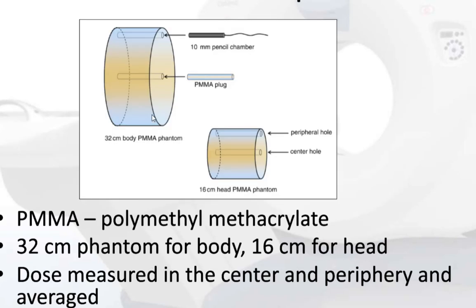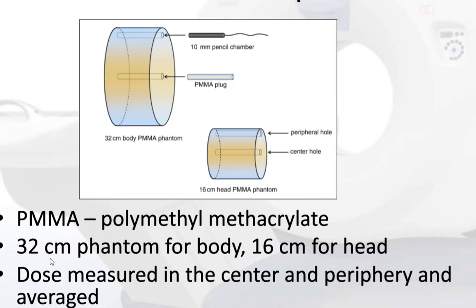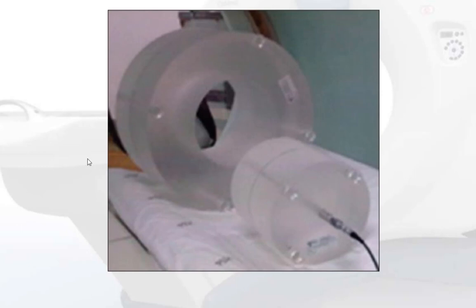The phantoms used for QA by CT techs and physicists are made out of PMMA, or polymethylmethacrylate. The 32 cm phantom is used for body scans and the 16 cm phantom is used for head CTs. Dose is measured in the center and periphery and averaged; dose in the periphery is higher than in the center. Here is also the pencil ionization chamber.